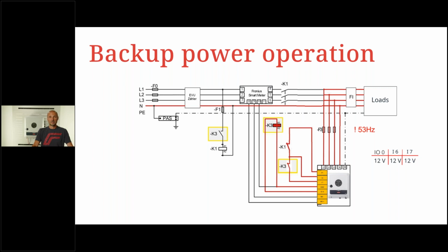Because otherwise, if grid would come back very soon for a short moment again, the contactor would close again, and that's not good, of course. So we need to avoid this. Therefore, we have the K3 open contact here to interrupt this line here. So in this case, when we have all the feedbacks, we will then start with full backup operation, and the inverter would start again with the 53 Hertz to supply the backup power loads.